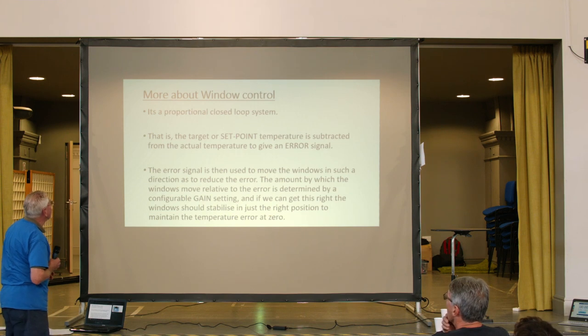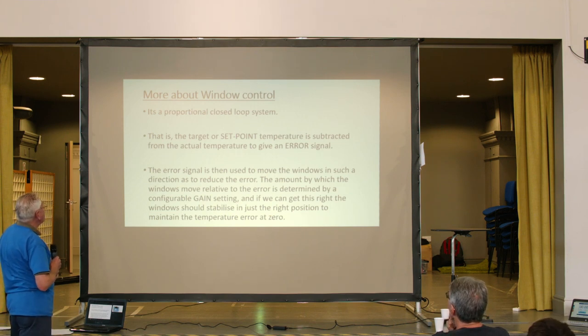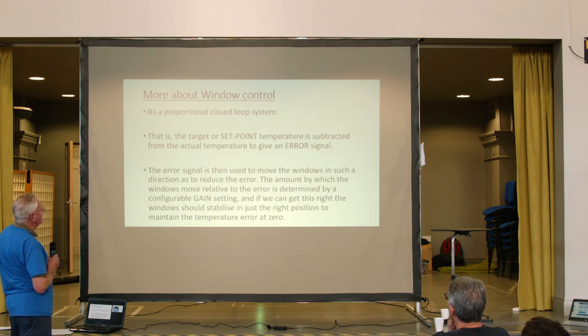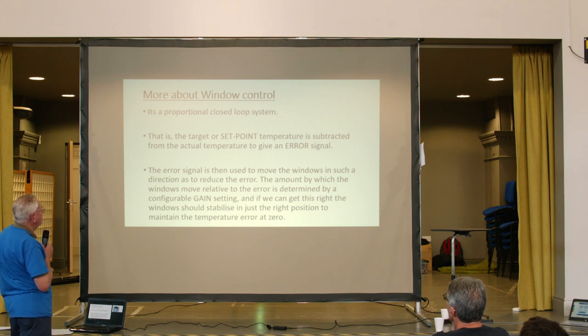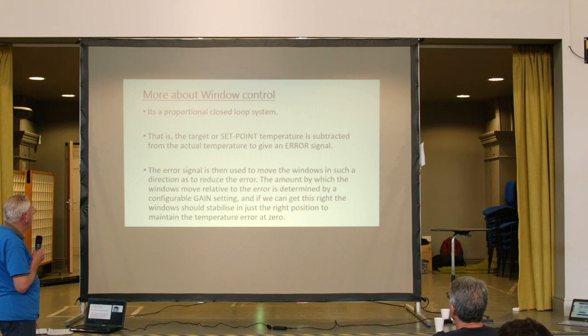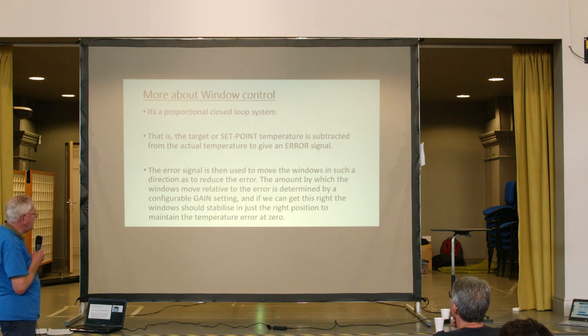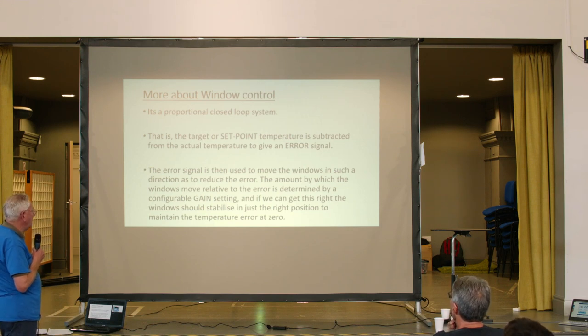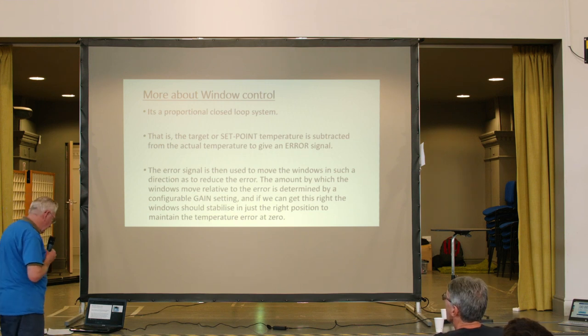Just a bit about window control — it's a proportional closed loop system. It has a target or set point for the temperature, which is subtracted from the actual temperature to give an error signal. The error signal is then used to move the windows in such a direction as to reduce the error. The amount by which the windows move relative to the error is determined by a configurable gain setting, and if we get that right the windows should stabilise in a nice intermediate position with a temperature error at zero.